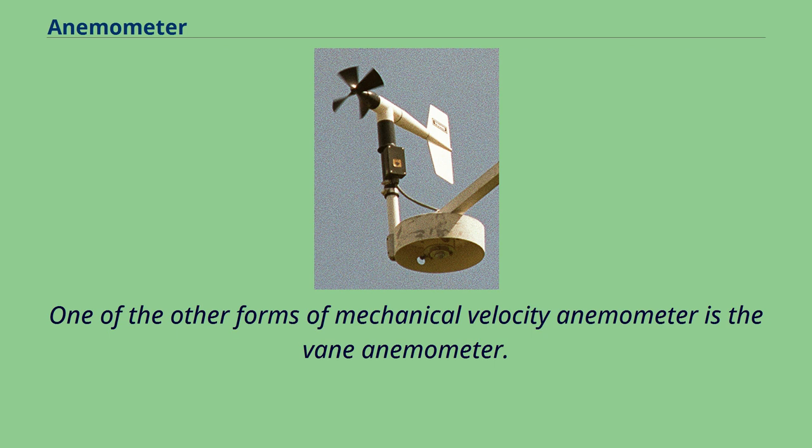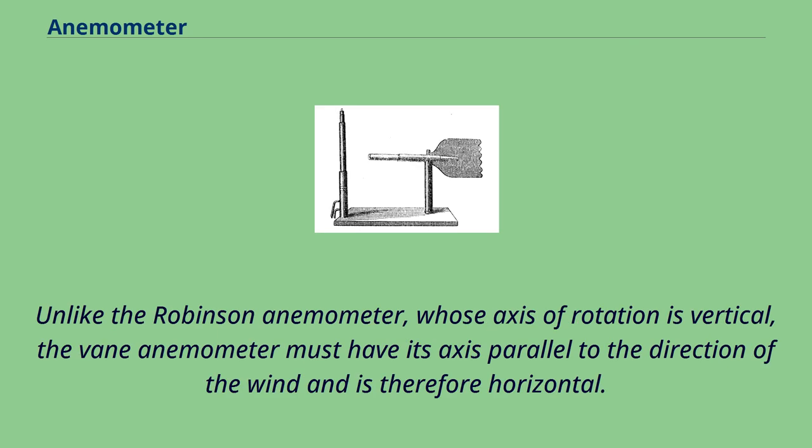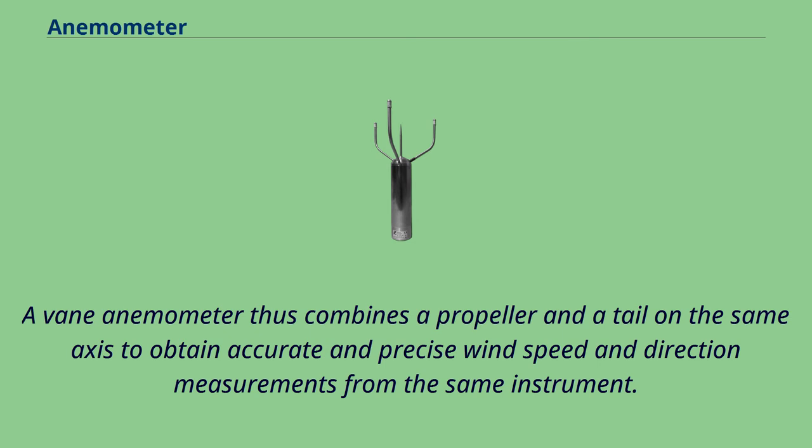One of the other forms of mechanical velocity anemometer is the vane anemometer. It may be described as a windmill or a propeller anemometer. Unlike the Robinson anemometer, whose axis of rotation is vertical, the vane anemometer must have its axis parallel to the direction of the wind and is therefore horizontal. Furthermore, since the wind varies in direction and the axis has to follow its changes, a wind vane or some other contrivance to fulfill the same purpose must be employed. A vane anemometer thus combines a propeller and a tail on the same axis to obtain accurate and precise wind speed and direction measurements from the same instrument.